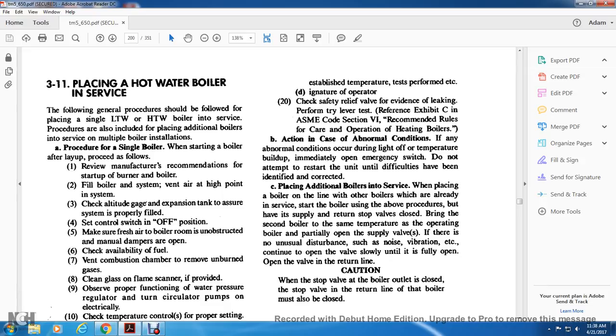Placing additional boilers into service: when placing additional boilers in service, open the valve slowly until fully open. Caution: when the stop valve at the boiler outlet is closed, the stop valve in the return line to the boiler must also be closed.